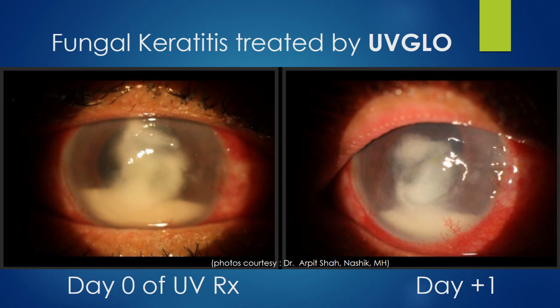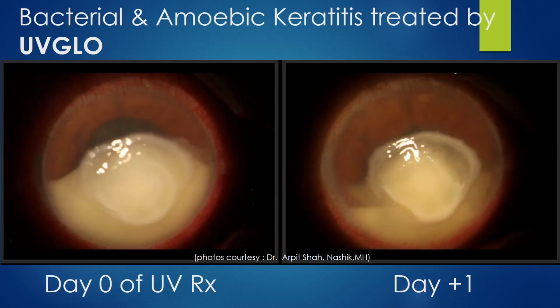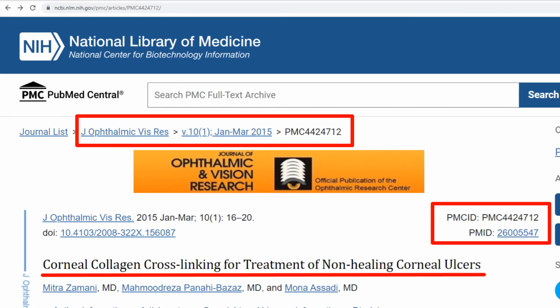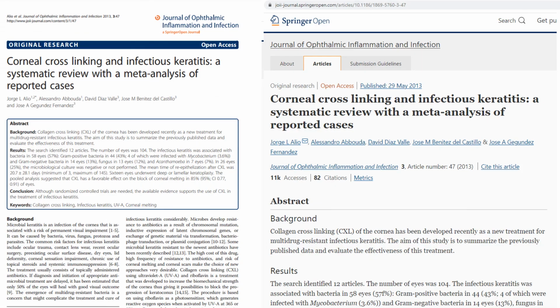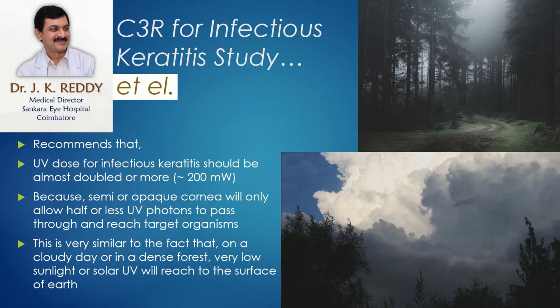Uvglo can also be used to treat fungal keratitis as well as bacterial and amoebic keratitis. There are several research publications which are now openly available about C3R for corneal ulcers treatment. This is a compiled and composite study of 12 publications about corneal cross-linking for infectious keratitis. Dr. J.K. Reddy and his group recommends that UV dose for infectious keratitis should be almost doubled or more, around 200 milliwatt, because semi or opaque cornea will only allow half or less than half of UV photons to pass through and reach the target organisms.